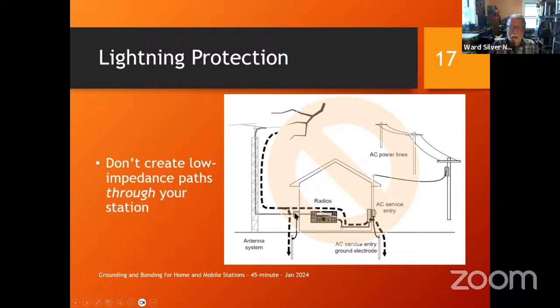But the lightning's going to flow like any other current—in every path available to it. Well, here's a nice path: you've got all these heavy cables going into your station, and your station is plugged into a branch circuit, and that branch circuit has a ground in it, which goes over to your AC service entry, and there's a ground rod there. So you've given lightning a tremendous path right through your station, through your AC service, to the ground. That can cause a lot of damage.